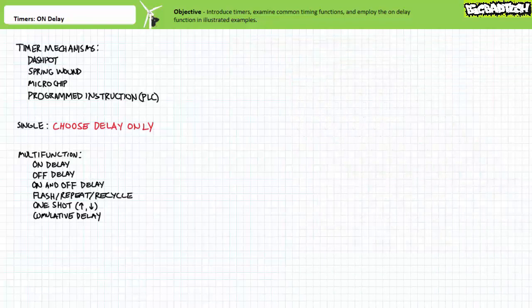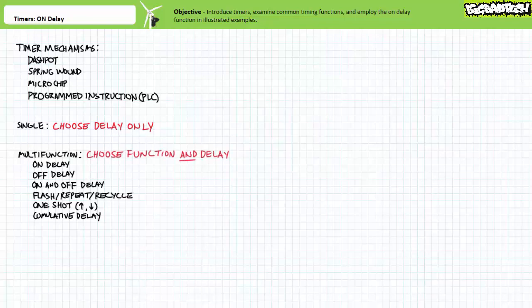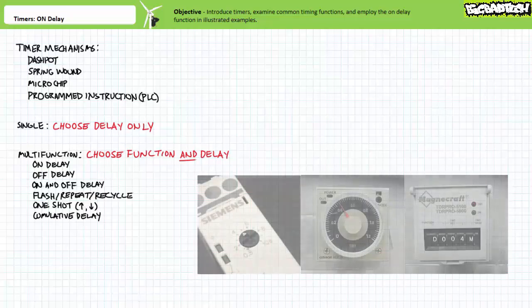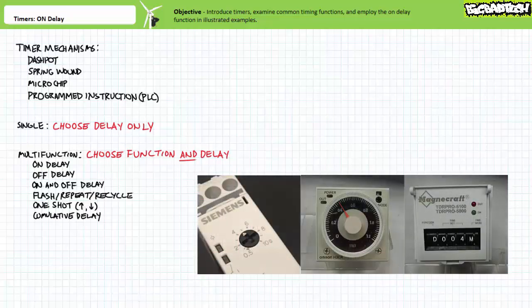A multi-function timer, in contrast, can perform several different functions, though it might be slightly more expensive. A multi-function timer could execute the on-delay, off-delay, on-and-off-delay, flash, repeat or recycle function, rising or falling-edge one-shots, cumulative on-delays, and more. To set up a multi-function timer, a technician must first choose the correct function and then set the delay period. Note certain asymmetric timer functions use two independently adjustable time periods, necessitating two delay adjustments. The user-selectable functions and delay period are ordinarily adjustable via a potentiometer screw, dial, or thumb wheel.